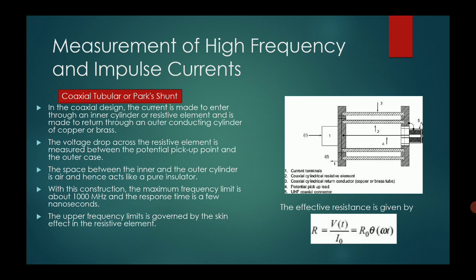The coaxial tubular or Park shunt: in the coaxial design, the current enters through the inner cylinder of the resistive element and returns via the outer conducting cylinder of copper or brass. The voltage drop across the resistive element is measured between the potential pickup point and the outer case. The space between the inner and outer cylinder is air, acting as a pure insulator. With this construction, the maximum frequency limit is about 1000 MHz and the response time is a few nanoseconds. The upper frequency limit is governed by the skin effect of the resistive element.